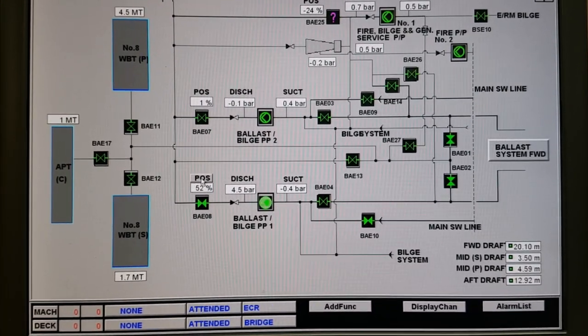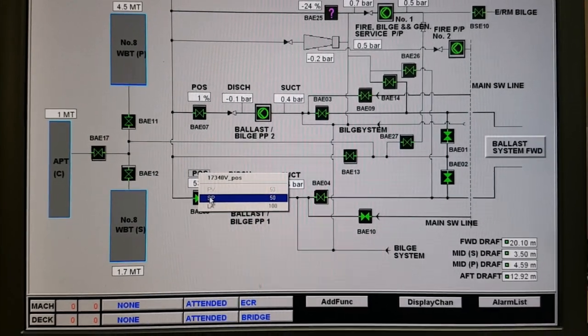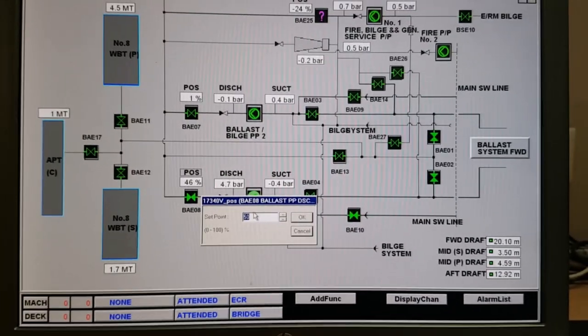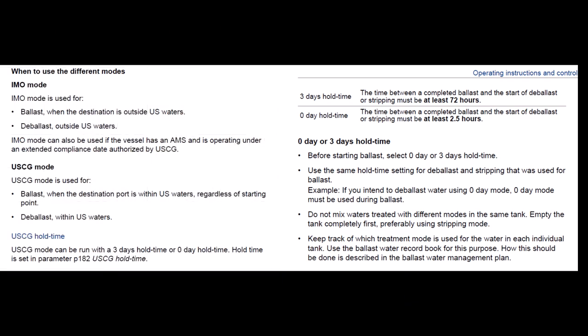At this point, an interesting thing applies regarding holding time before uptake. The ballast treatment system will ask you what method you intend to use: three days or zero days. Three days means the time between a completed ballast and the start of deballast or stripping must be at least 72 hours.